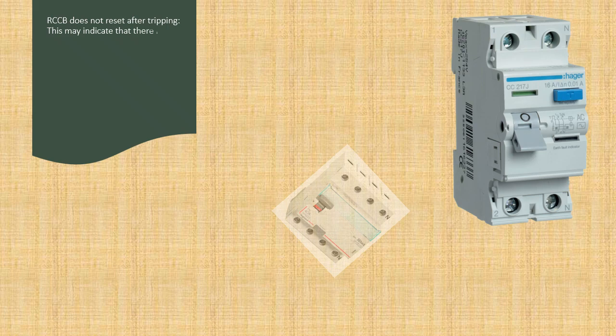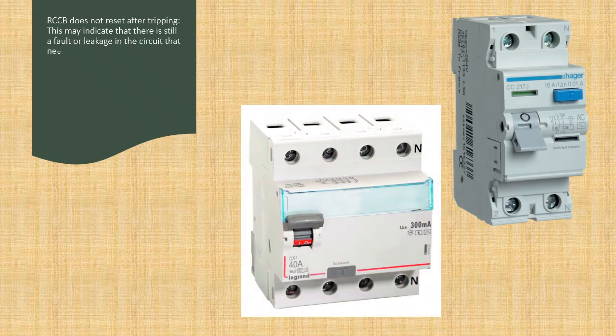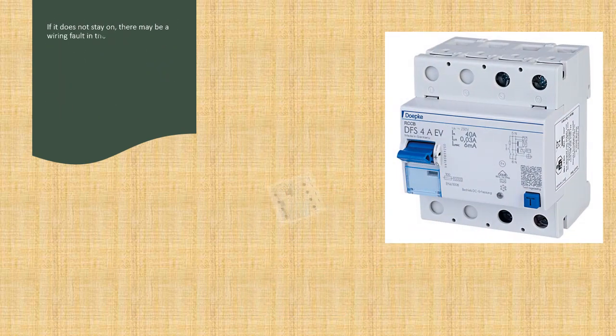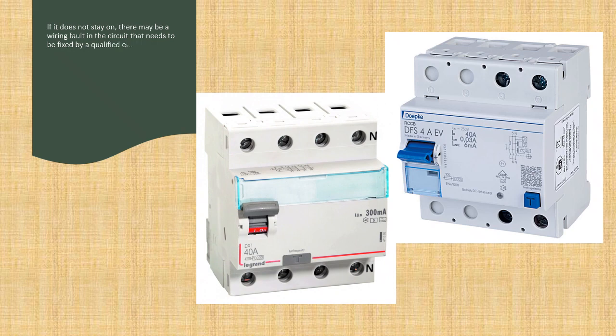RCCB does not reset after tripping. This may indicate that there is still a fault or leakage in the circuit that needs to be cleared before resetting the RCCB. To reset the RCCB, turn off the power and disconnect all appliances from the circuit. Then turn on the power and push the lever of the RCCB to the on position. If it does not stay on, there may be a wiring fault in the circuit that needs to be fixed by a qualified electrician.